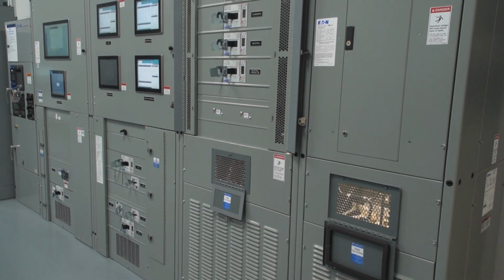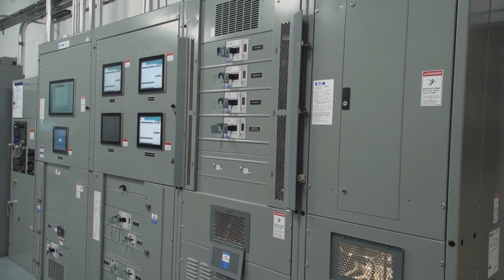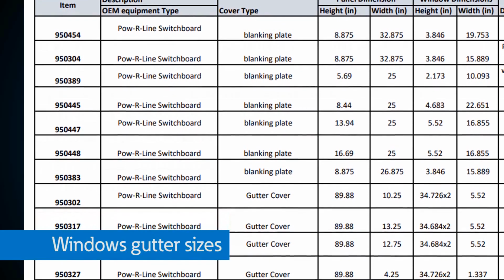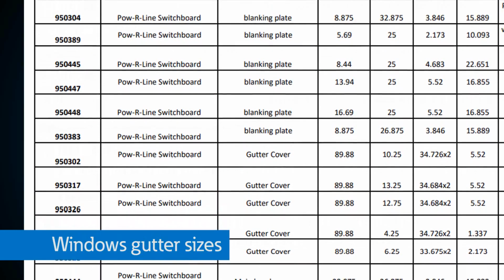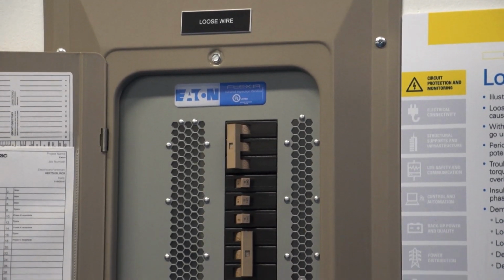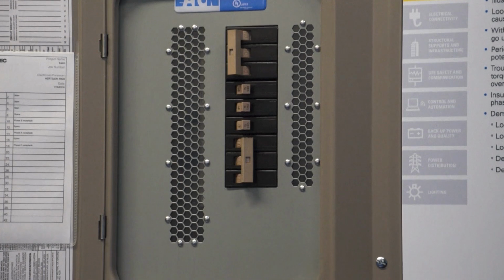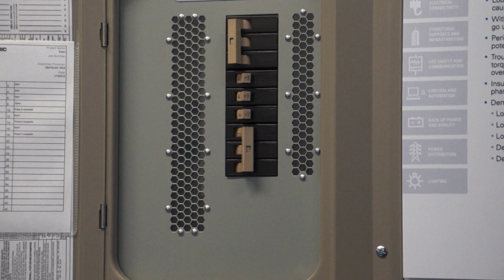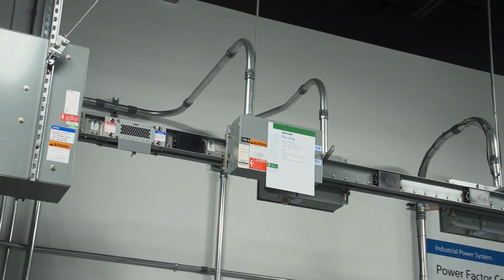This layout, for example, shows some great options for replacement gutters or covers with IR windows mounted on a switchboard. These windows are now available for standard and custom sizes of covers and gutters. For panel boards, consider replacing a cover with one of these IR windows that would allow you to scan all of the connections of the breakers, which is where most of the overheating or issues occur. For busway, here's an example of the termination points that might be worth monitoring over time. For existing equipment, almost all of these options can be retrofitted during routine maintenance with standard legacy equipment using standard size replacement covers or custom covers designed to match the equipment.